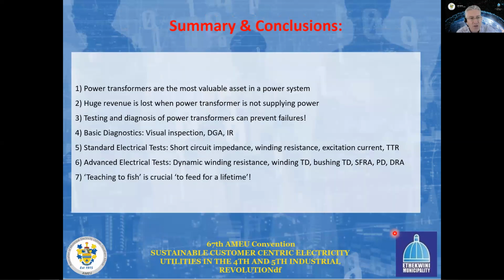So to summarize and to conclude, power transformers are one of the most valuable assets in our power system. Huge revenue is lost when power transformers are not supplying power. Remember the 1 million rand per day for a 20 MVA transformer, for instance. Testing and diagnosis of the power transformers can prevent failures. There are basic diagnostics available, such as visual inspection of the transformer, dissolved gas analysis, as well as insulation resistance measurements that can be done on a regular basis on your transformers.